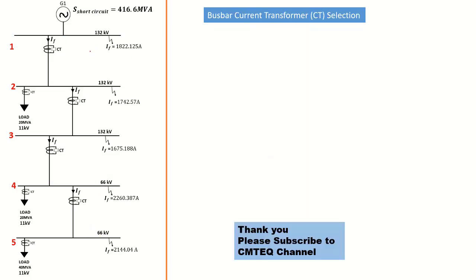Now that we've already determined the maximum short circuit current for each one of these busbars, please notice the patterns here. We had a higher voltage here, so the current was slightly smaller. Now as the voltage went down via this transformer, because remember there is a transformer at this point here.